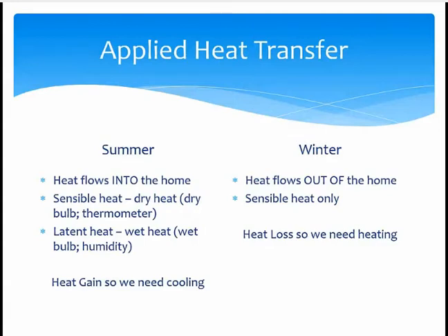So the reason that we do a load calculation is because of the heat transfer we saw in the previous illustration. In summer, heat flows into the home, and there are two types of heat. There's sensible heat, which is dry heat — the temperature that we see on the thermostat, or the dry bulb temperature. There's also latent heat. However, this is the wet heat, and it's the one that we associate with humidity, and we also call it the wet bulb temperature.